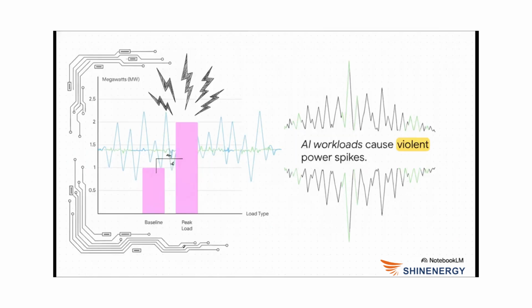Now, what's really fascinating about this is the unique behavior of AI computers themselves. AI doesn't just sit there sipping a steady, predictable stream of power. When a massive cluster of GPUs enters a learning mode, they operate in total synchronicity, and their power draw wildly pulsates. So a rack pulling a baseline of, say, 1 megawatt can suddenly spike to 2 megawatts, and it might do this 4 or 5 times a single second.